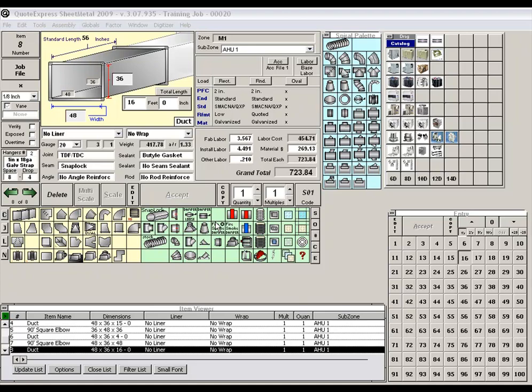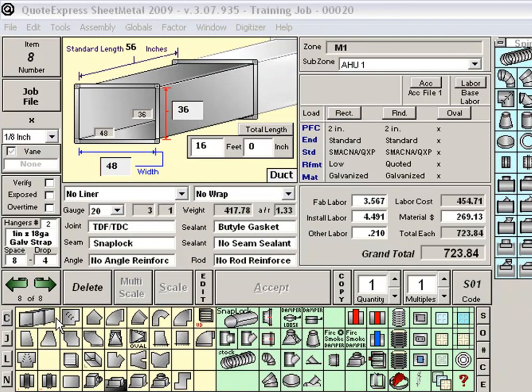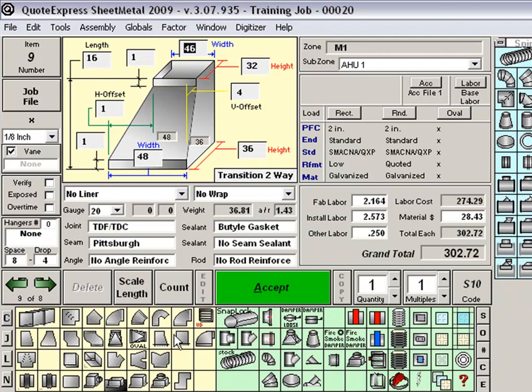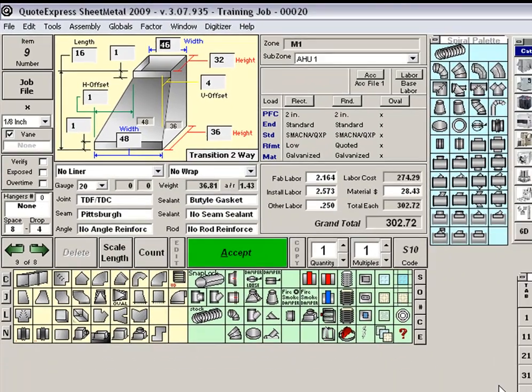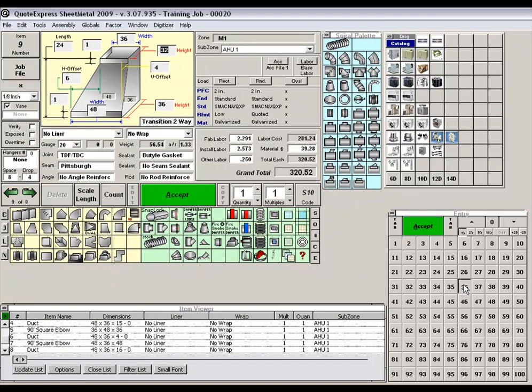Following the duct is a transition, changing us from 48 by 36 to 36 by 24. Select the two-way transition directly below the duct. You'll see that the large end is filled in with the previous dimensions, 48 by 36, automatically filling in for you. The program then highlights the exit dimensions, or the top side, for you to put in what dimensions you're going to. Move to your entry pallet, click the 36, and then the 24. You can also put in a length at this time. Let's make it 24 inches long, and then click the Accept.